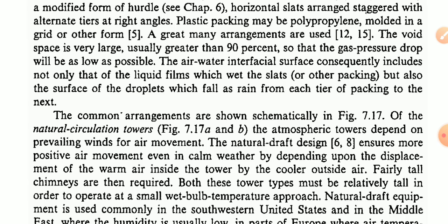The void space is very large, usually greater than 90%, so that the gas pressure drop will be as low as possible, and the air-water interfacial surface is consequently increased. It includes not only the liquid films which wet the slats or other packing, but also the surface of the droplets which fall as rain from each tier of packing to the next.